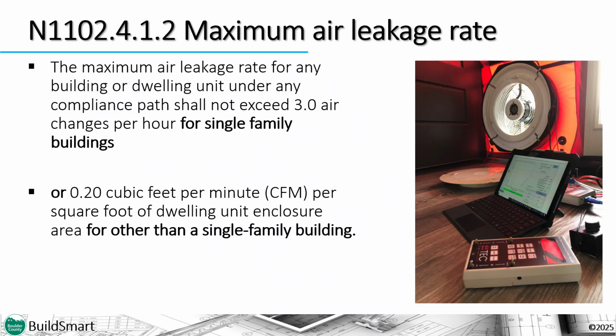The maximum air leakage rate for any building or dwelling unit cannot exceed 3 air changes per hour for single-family buildings. For dwelling units in multifamily buildings or buildings other than single-family buildings, the maximum air leakage rate cannot exceed 0.20 cubic feet per minute per square foot of dwelling unit enclosure area, a different metric. This means that buildings that are not considered single-family residential buildings use an alternative air leakage metric that depends on the size of the building and could be leakier than 3 air changes per hour.